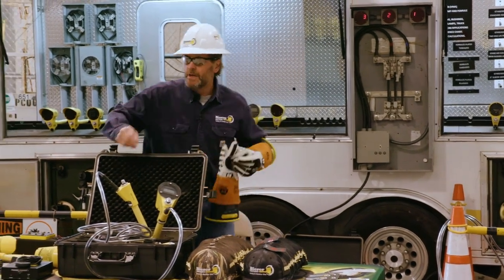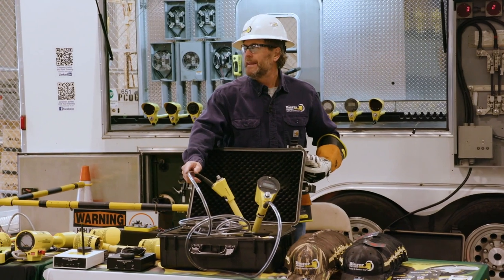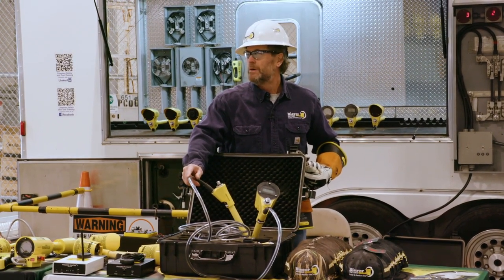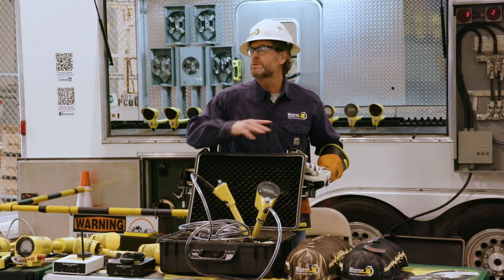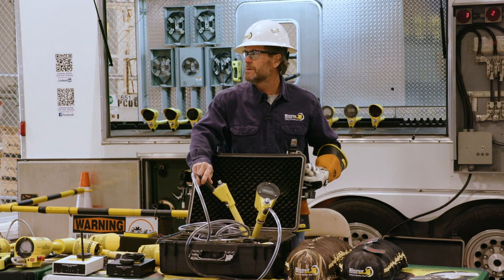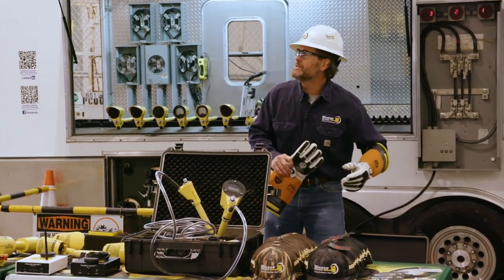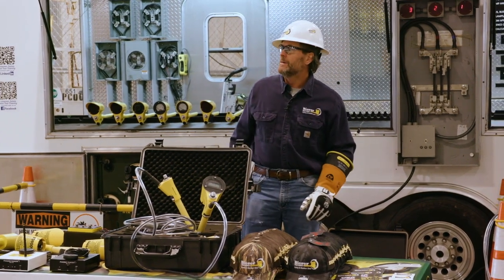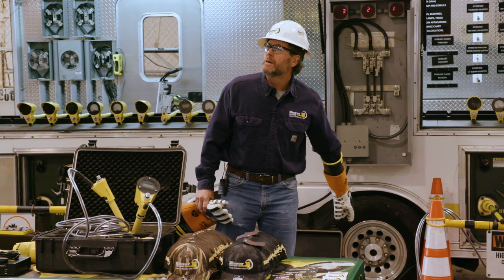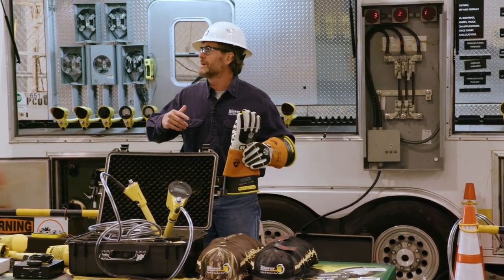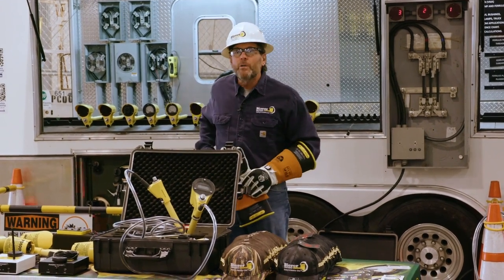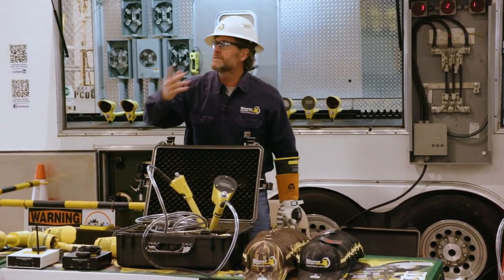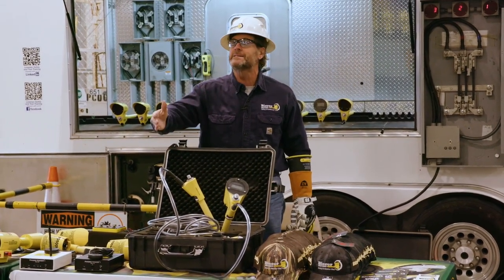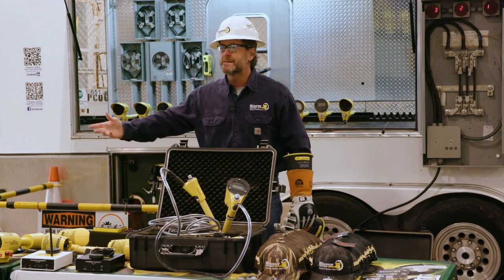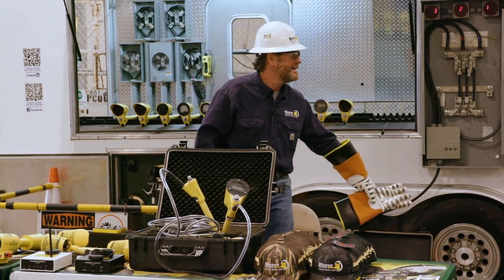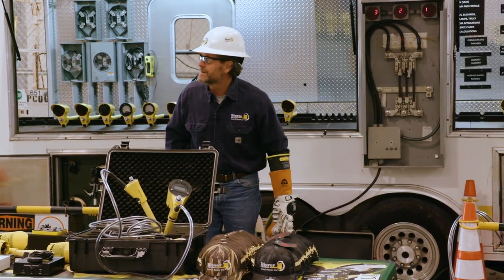This cable right here, we're the only company in the world that builds a cable within a cable. Nobody else does this. So all of our corded tools are shielded to 35,000 volts. So when we high-pot or phase using this tool, the cord can lay on the ground, but you want to stay away from that cord. It's part of the tool. Remember what we talked about, your air dielectric. So if you're trained to stay 31 or 36 inches back from the meter head, you also want to train and teach that you stay that same distance back from the cord. Make sense? Because that's part of the tool. It's energized. You can hear that? Robbie says it's energized because he can hear it's energized.